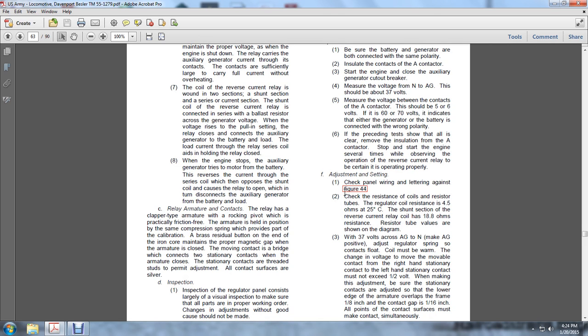The relay has a clapper type armature with a rocking pivot, practically friction free. The armature is held in position by a compression spring, which provides the calibration. A brass residual button on the end of the iron core maintains a proper magnetic gap. When the armature is closed, the moving bridge contact connects the two stationary contacts. The stationary contacts are threaded studs to permit adjustment. All contacts are silver.